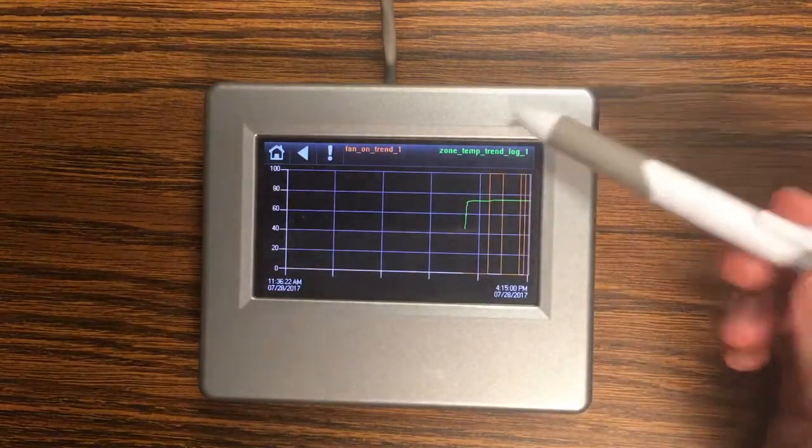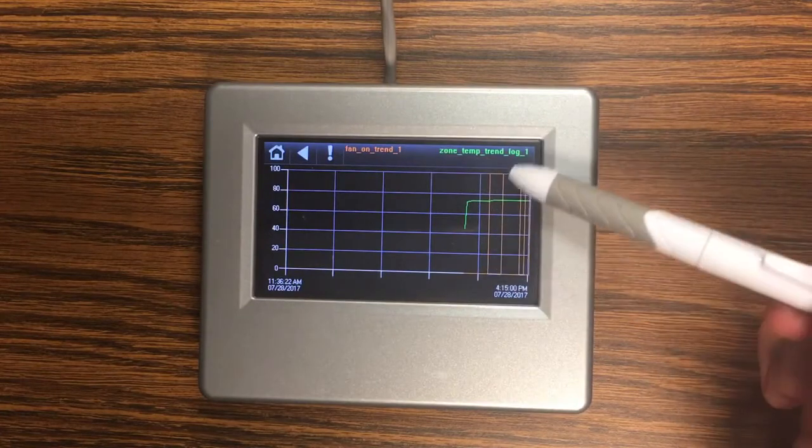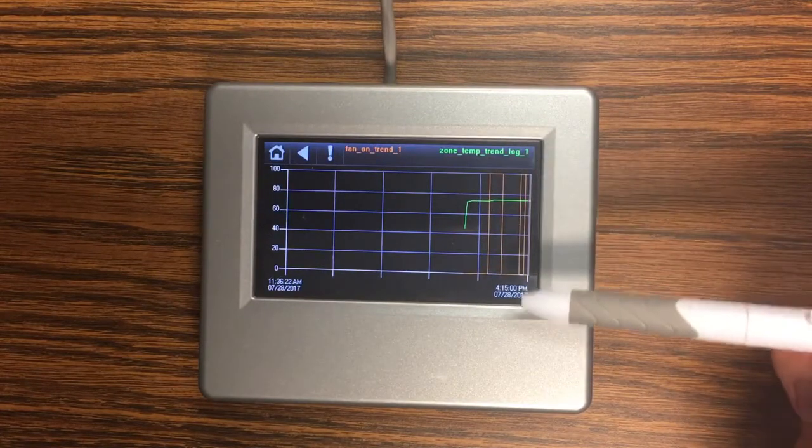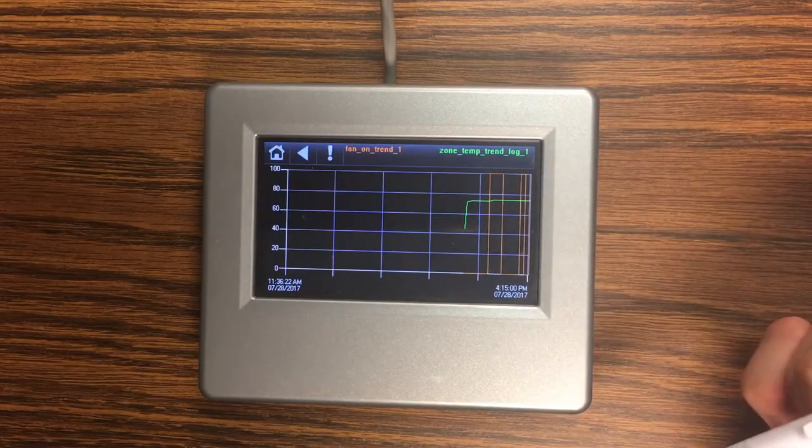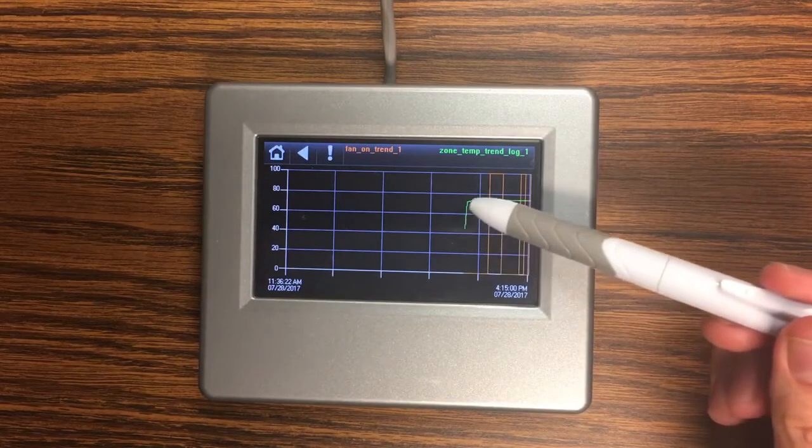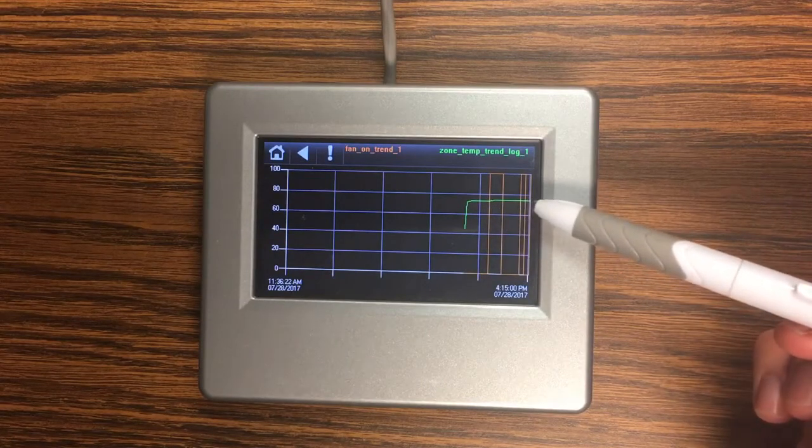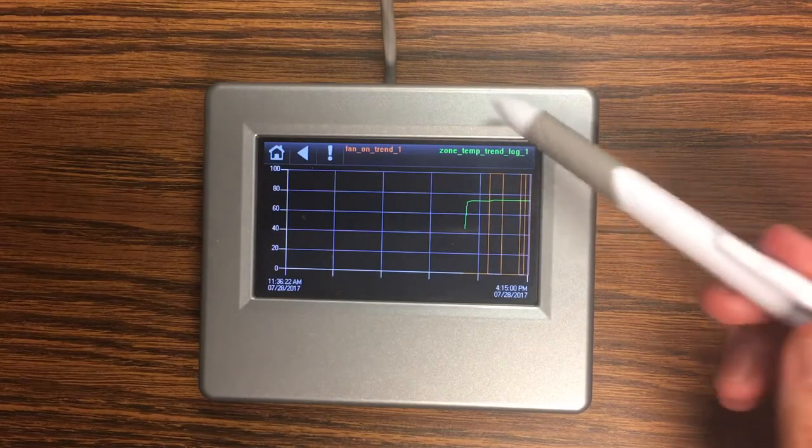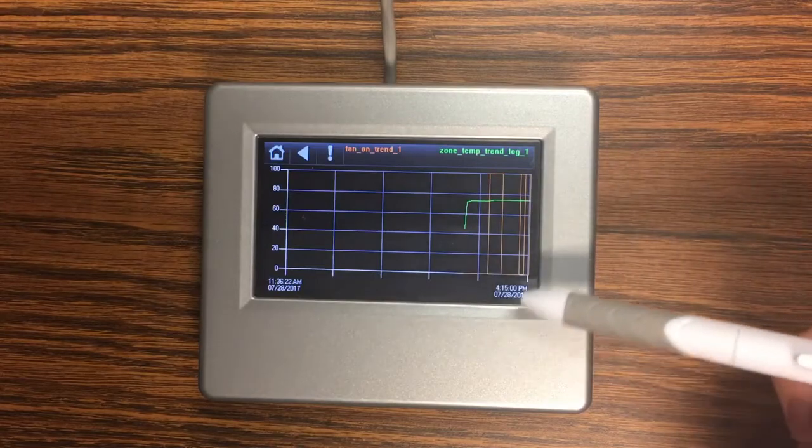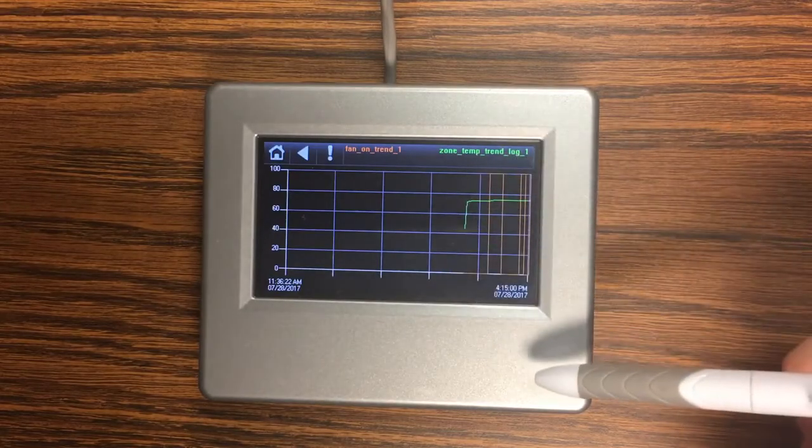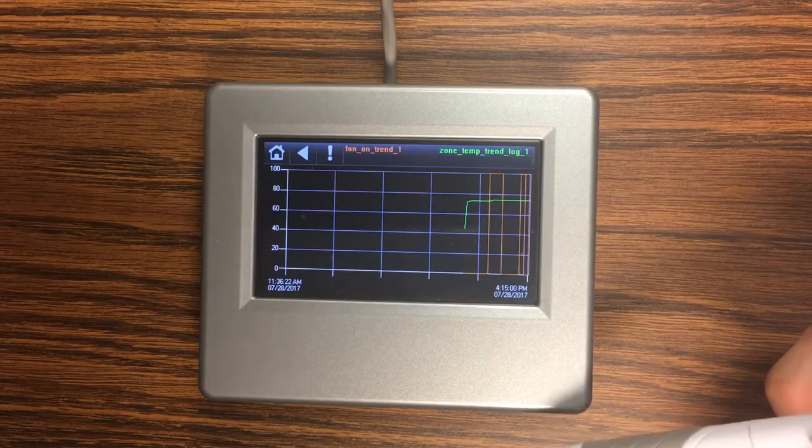And so you can see the orange is my fan on and you can see that's been turning on and off as we've been doing the demonstration. And then we can see our zone temp changing over time. So trends can be a really powerful tool when you're troubleshooting and trying to see what happened with your unit. Try to solve problems.